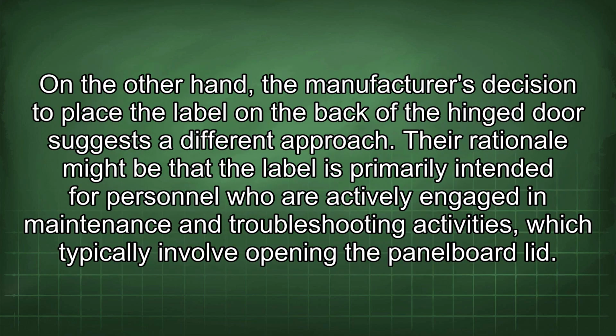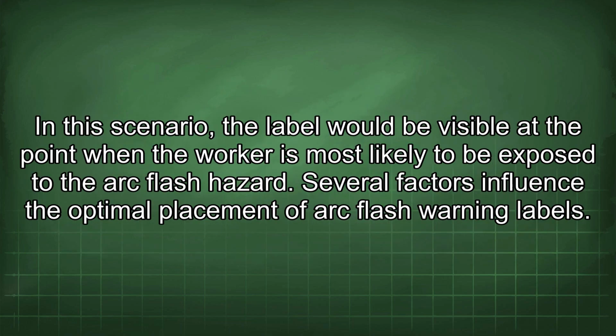On the other hand, the manufacturer's decision to place the label on the back of the hinge door suggests a different approach. Their rationale might be that the label is primarily intended for personnel who are actively engaged in maintenance and troubleshooting activities, which typically involve opening the panel board lid. In this scenario, the label would be visible at the point when the worker is most likely to be exposed to the arc flash hazard.